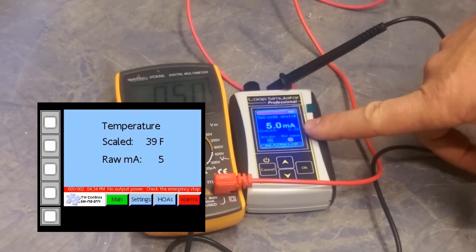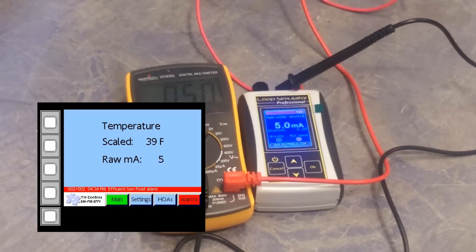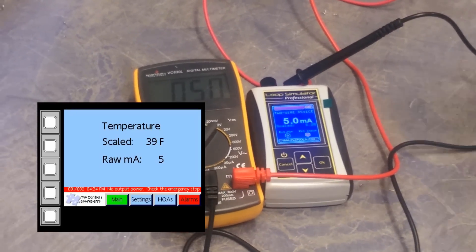We run up to five milliamps. You see we show five coming out. Our meter shows five. Our HMI shows five. And now our scale value is 39.